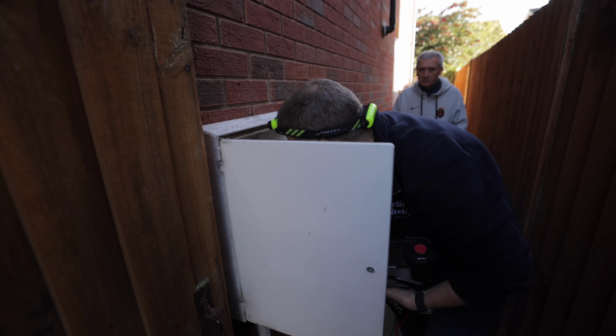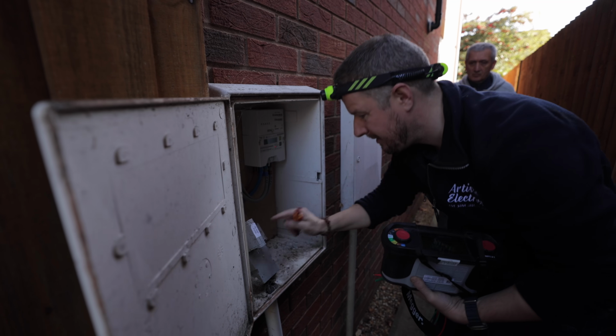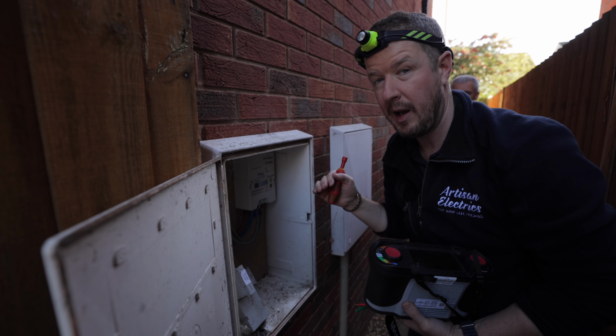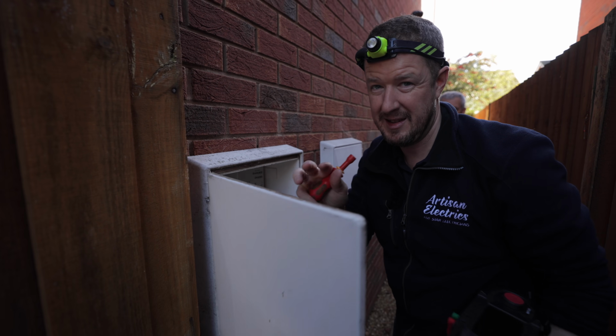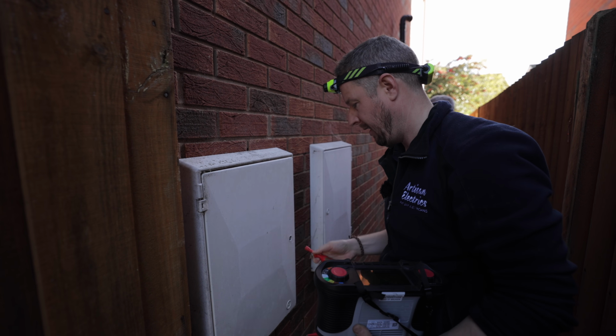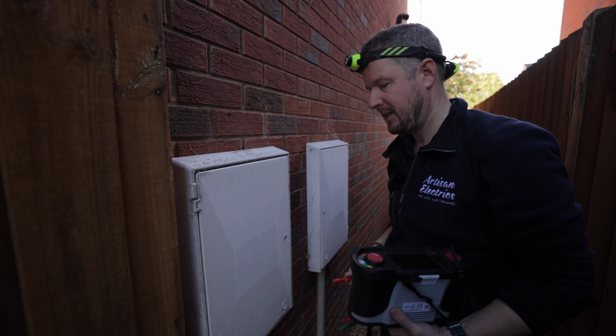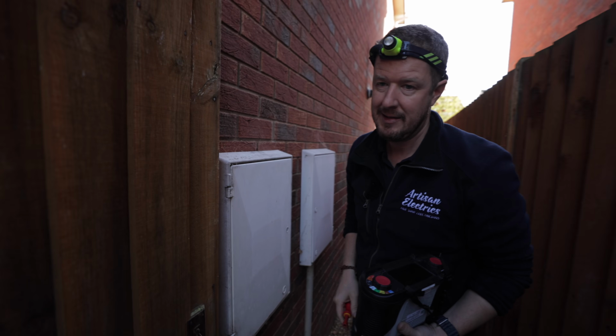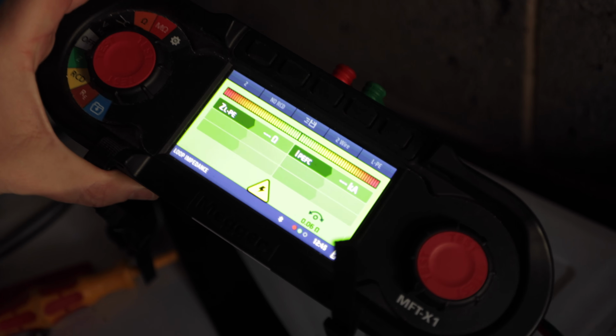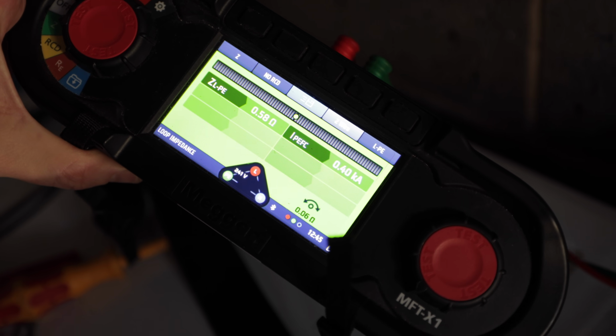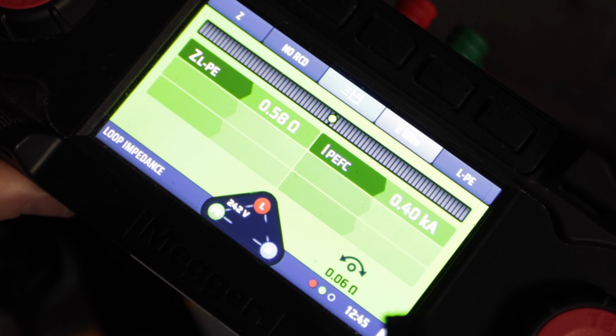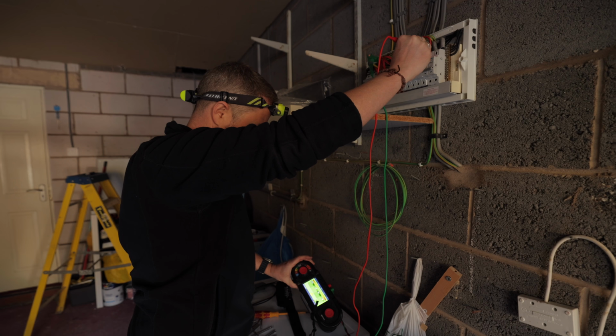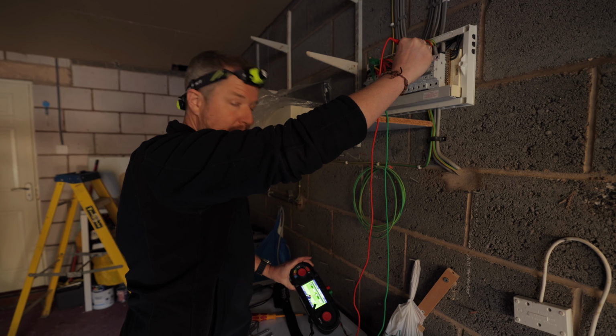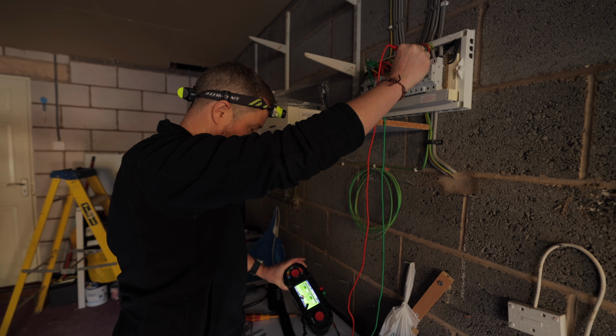Is the meter box just around here? Okay. Everything looks okay here. It is a TNCS system, so we'd be looking for a ZE of less than 0.35 ohms, and it looks like it is actually higher than that. So that's the next thing we need to check. This reading should be less than 0.35 and it's 0.58. So it is too high, which means we actually need to call UK Power Networks and report this to them.